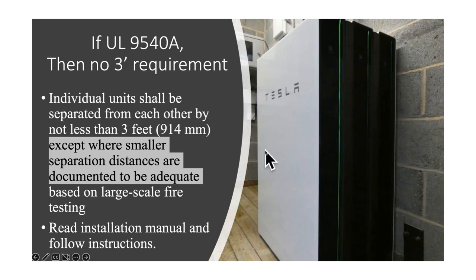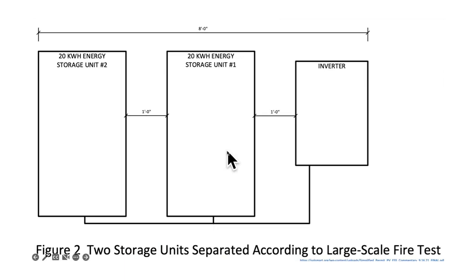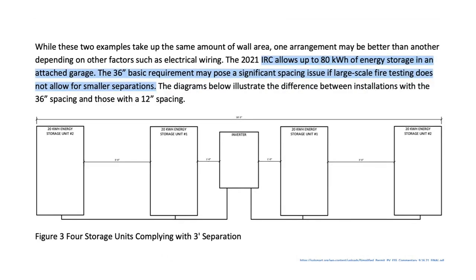There's 3 in a stack right there. Those all each have their own inverters in them, of course. And so if we did the large scale fire testing, we're just showing that it's closer than 3 feet and that that's okay. Here is just one of those worst case scenarios. And so like the IRC, we're going to look at these numbers, but it allows up to 80 kilowatt hours of energy storage in an attached garage.